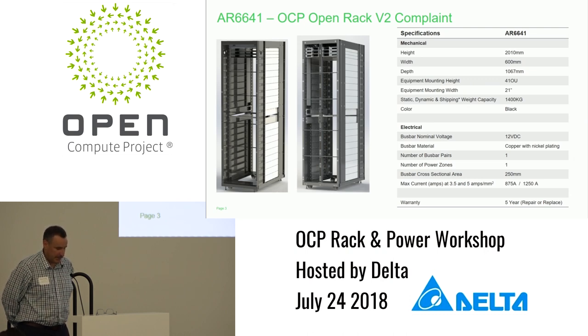It's been tested up to 1,400 kilograms both dynamic and static. For the electrical, it's 12-volt DC, one bus bar, one zone, and a 250 square millimeter cross-sectional area, which gives you about 875 amps. It's intended to be compatible with the power shelf we submitted, which is a 15 kW unit that I'll show in a second.